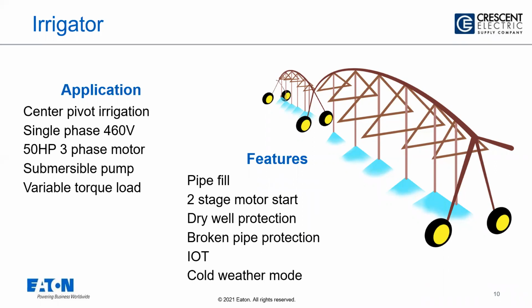And the drive has some inherent features that are pretty useful for an application like this. It has a pump fill application. We'll talk about it. It's for priming when there is no water in the pipes and to avoid water hammering. The second one, it can generate 2-stage motor starts. We'll talk about it too in the coming slides. Dry well protection to protect the pump in case of dry running. There is an inherent feature built in, and it also has broken pipe protection to avoid flooding in the fields. We have a feature built in the drive.